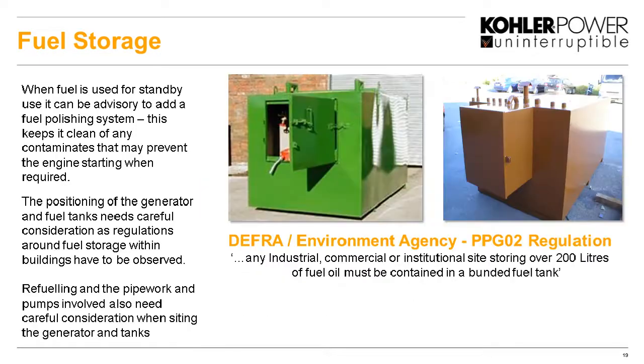So when we have a separate fuel tank, some examples here, we have to make sure we get this plumbed in correctly. Obviously there's going to be pipe work, there's going to be pumps, and that decides where the generator is going to be sited and where the fuel is going to be sited, of how we're going to get the fuel first of all from the fuel tank to the engine, but also we have to consider refueling the tank. So there's going to have to be pipe work for that possibly, especially if it's inside a building.